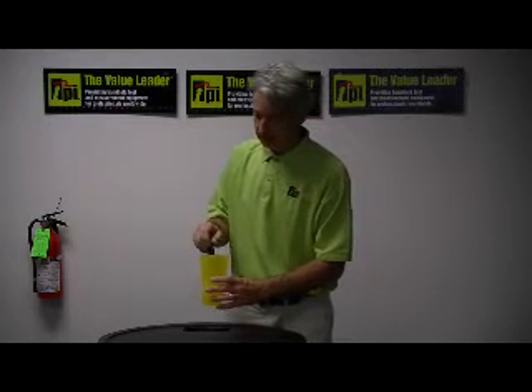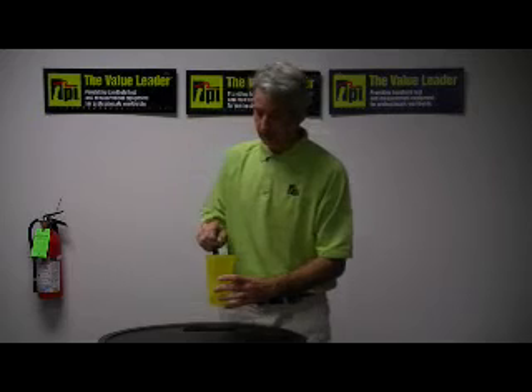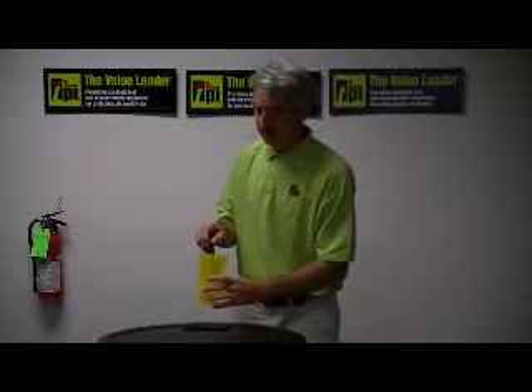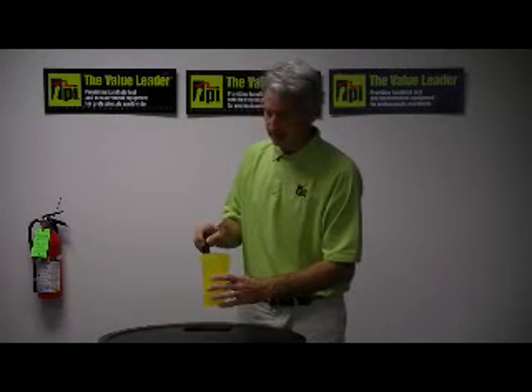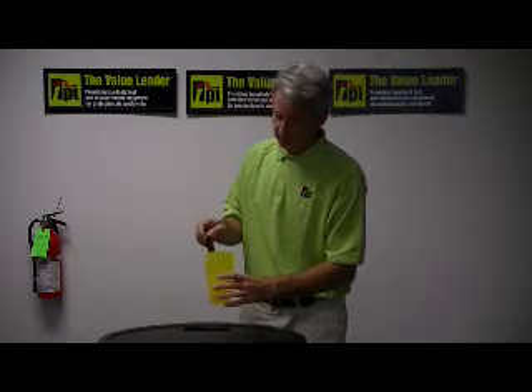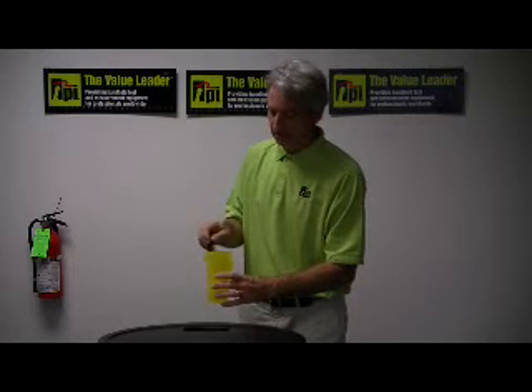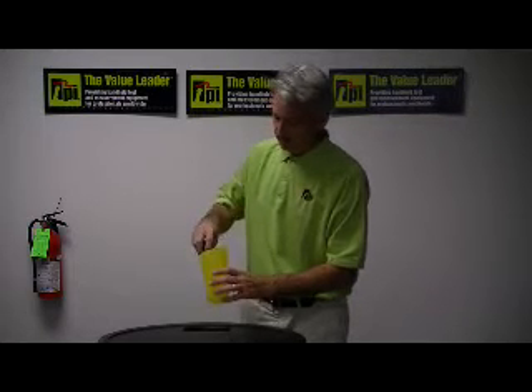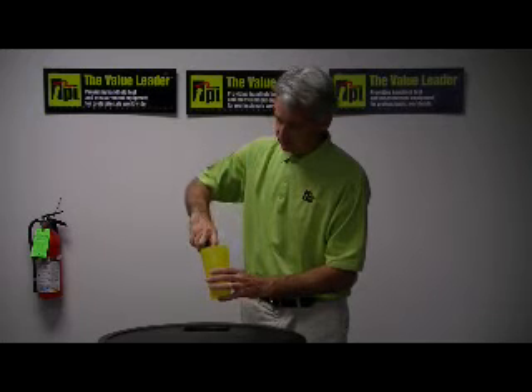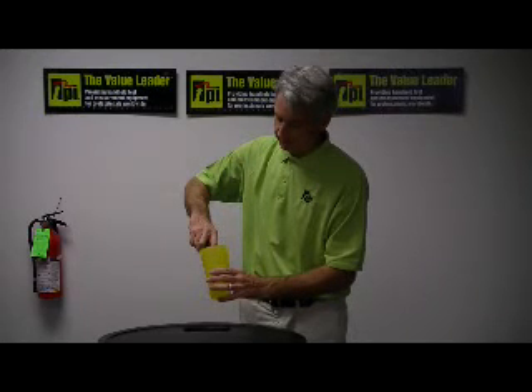As soon as the reading on the thermometer stabilizes, I simply press and hold the DH CAL button, which stands for the Data Hold Calibration button, and in approximately 8 seconds, the unit will calibrate itself automatically.